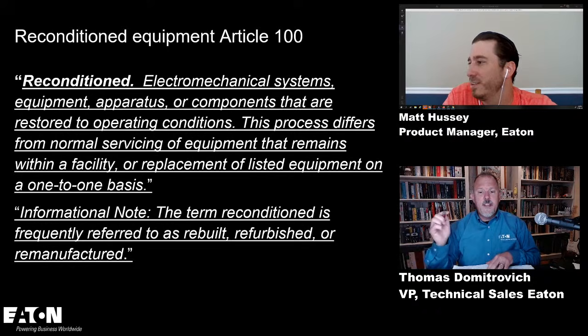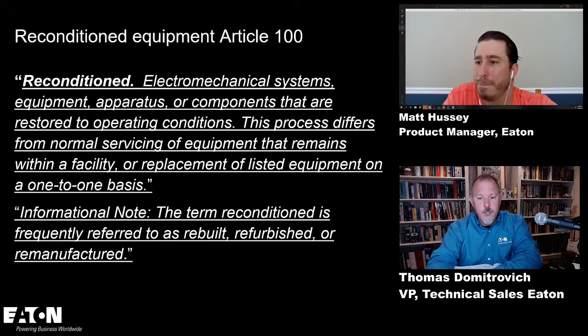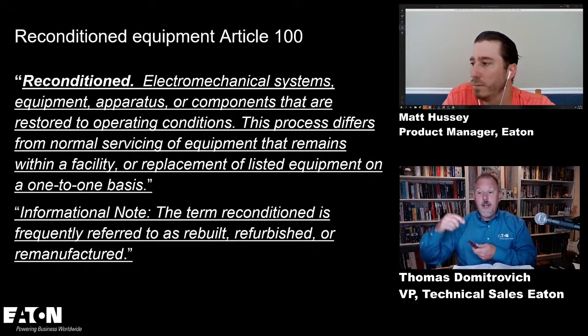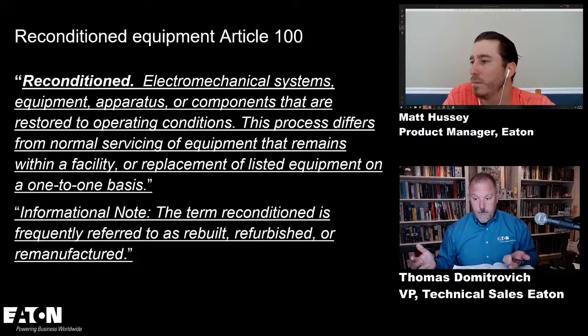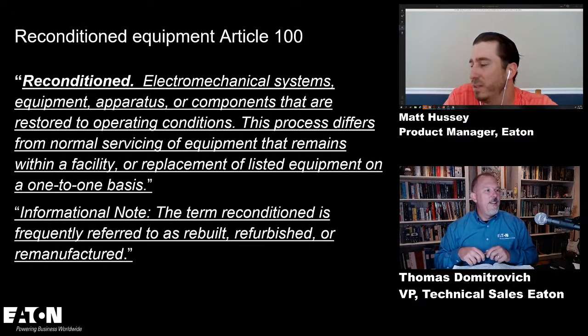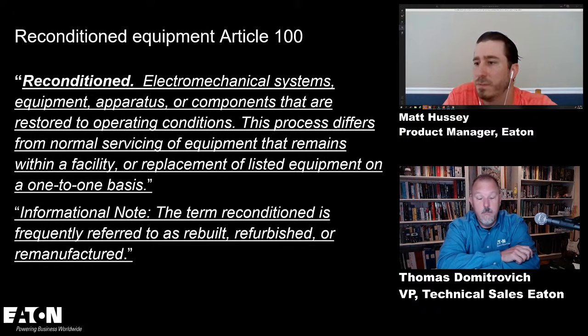All right. And now the definition in 100 says it differs from normal servicing of equipment that remains within a facility or replacement of listed equipment on a one-to-one basis. So that answers the first question: if I had a failed motor starter and I take the old one out and put the new one in, that wouldn't be reconditioning. If it's a one-for-one. Now, if I took your starter out and I put a Square D starter in, can I do that? If I don't have a combination for any of those, you're probably not going to have that short circuit combination rating.